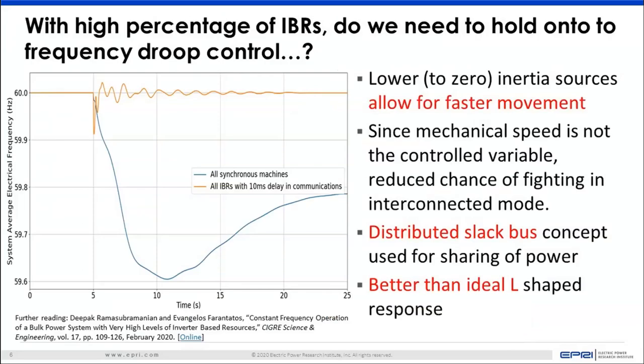Now, what we started doing was that if we do go about this scenario where we have a lot of the generation resources being inverter-based resources, and even recognizing that there might be a few milliseconds delay in communication, and there is filtering time, and there is delay in measurement of frequency and whatnot, because of the fact that these are rapidly moving devices, allowing for faster movement of these devices makes us ask the question, do we still really need to hold on to frequency droop control?